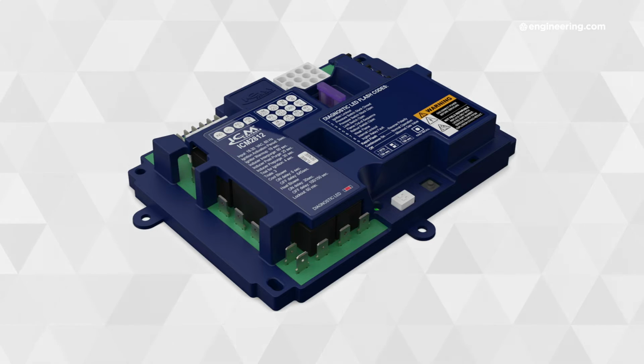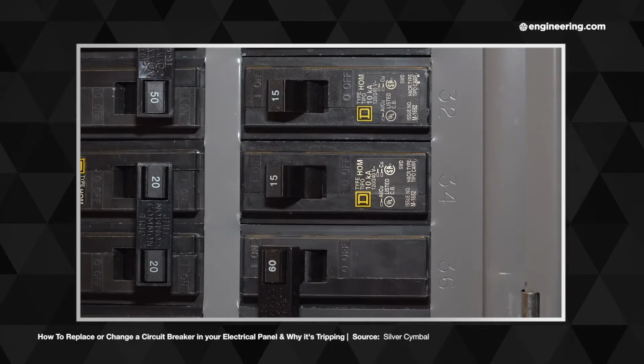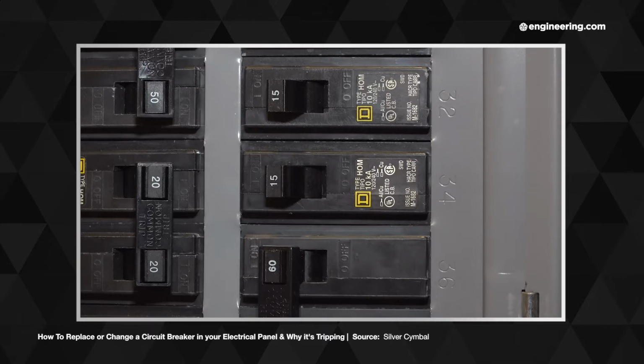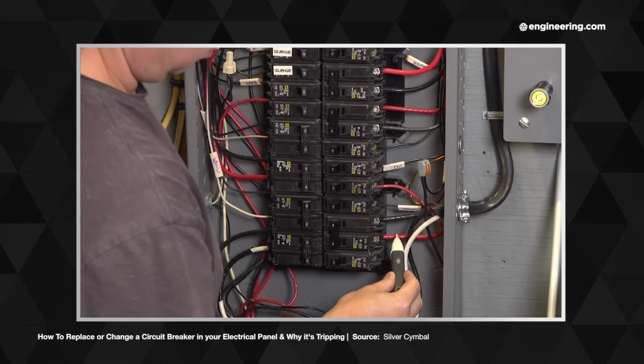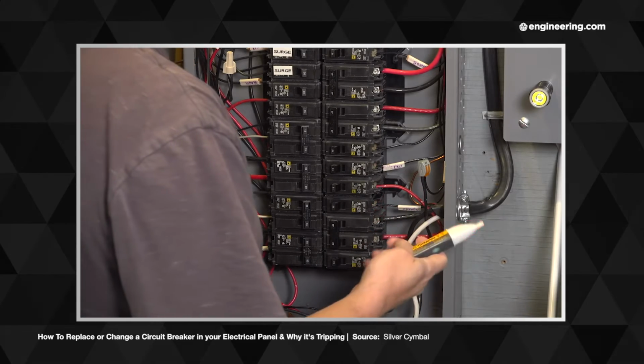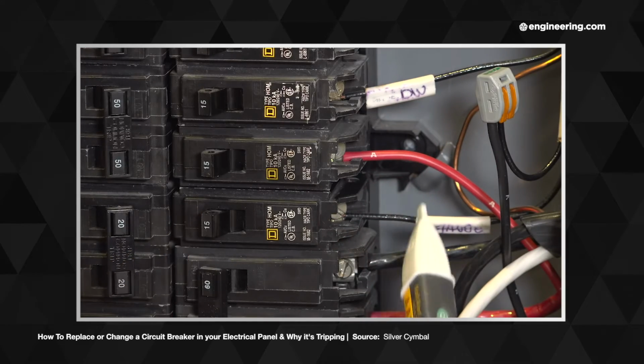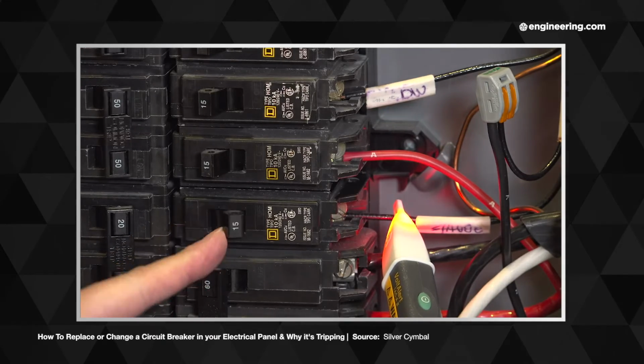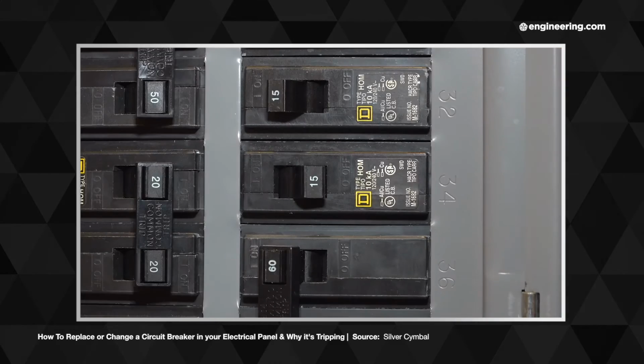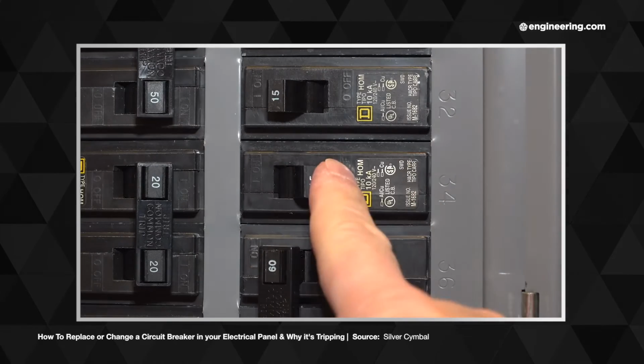Now would a circuit breaker be better? It would certainly be easier to reset than replacing this fuse, but it has several disadvantages. It's more complex, more expensive, and is itself a potential point of failure. Its very convenience makes it possible to ignore transients or occasional shorts by resetting at the push of a button, which is not exactly conducive to good MRO.